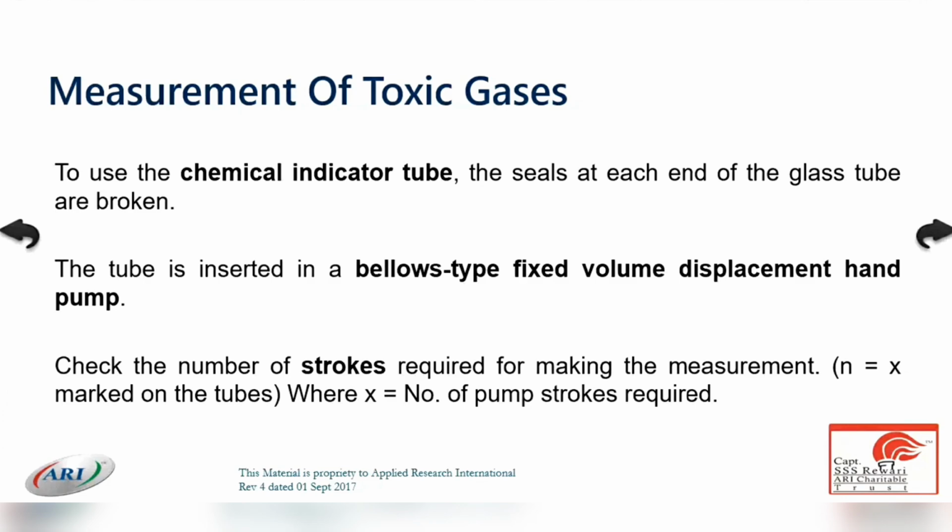As far as chemical tankers are concerned, these indicator tubes must be there for all kinds of gases present in the cargo tank. Other than this, you have a fixed gas detection system installed on board, measuring 24 hours. These fixed instruments measure the gas percentage in each individual compartment.